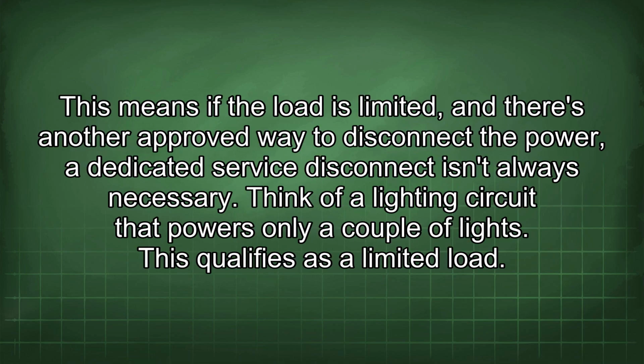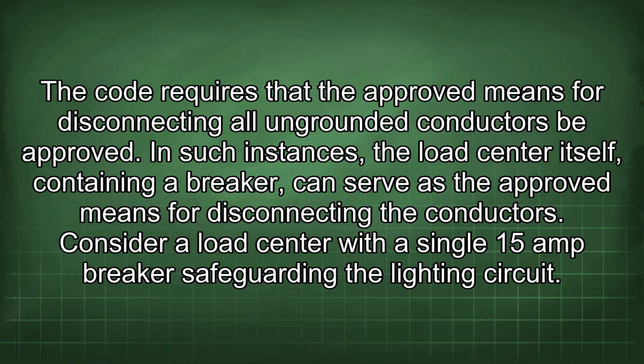This means if the load is limited and there's another approved way to disconnect the power, a dedicated service disconnect isn't always necessary. Think of a lighting circuit that powers only a couple of lights. This qualifies as a limited load. The code requires that the means for disconnecting all ungrounded conductors be approved. In such instances, the load center itself, containing a breaker, can serve as the approved means for disconnecting the conductors.